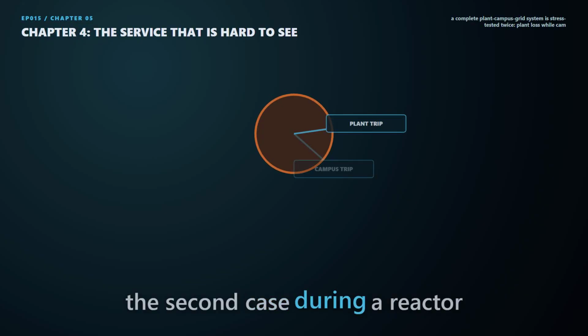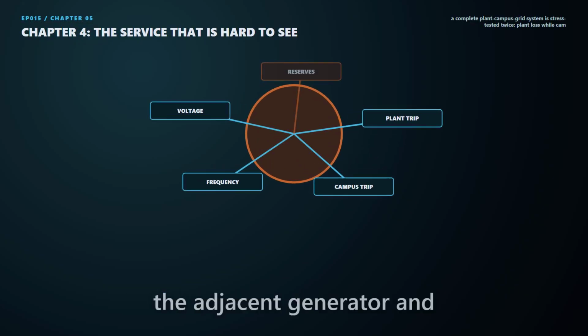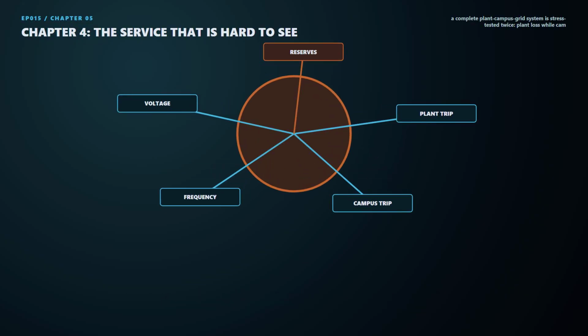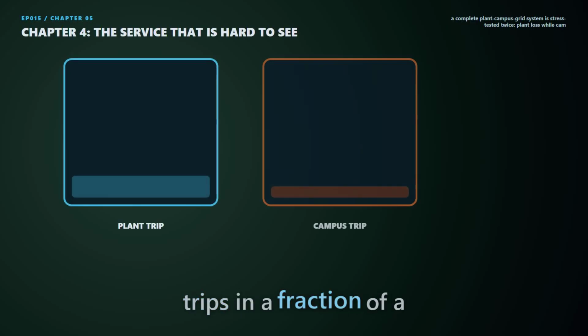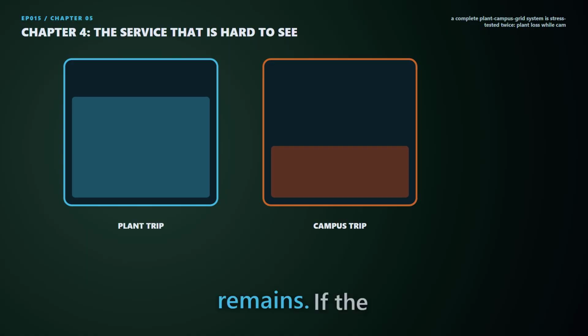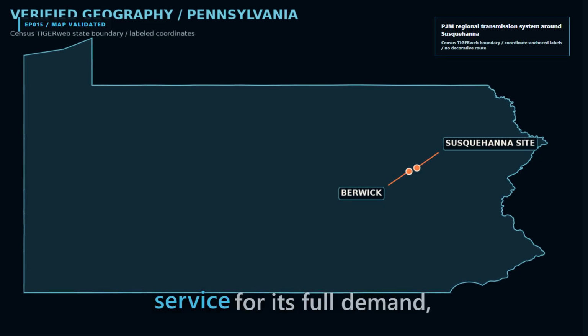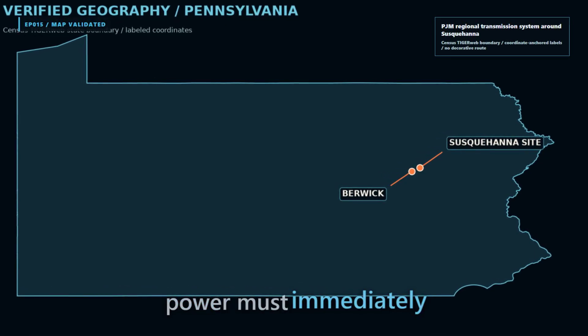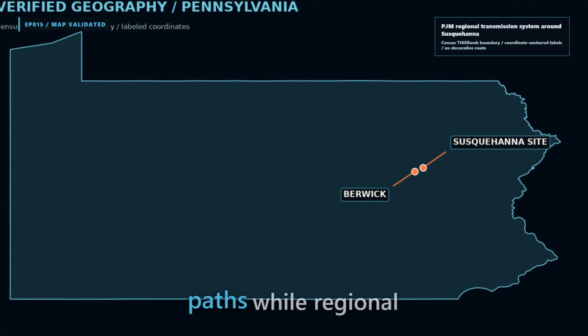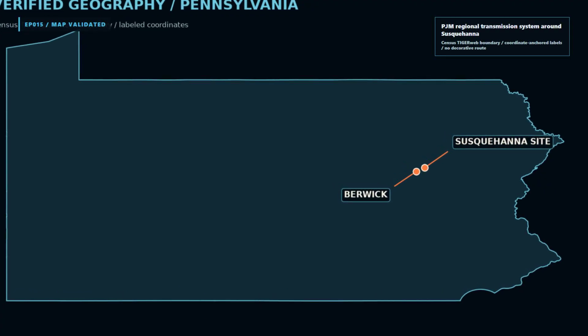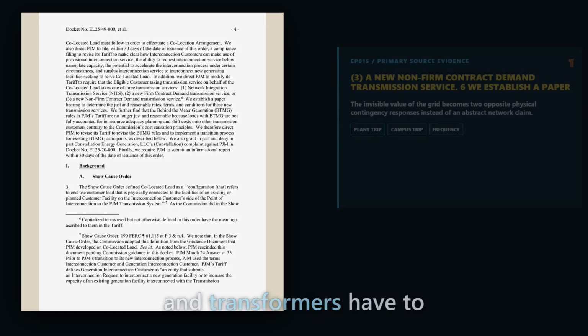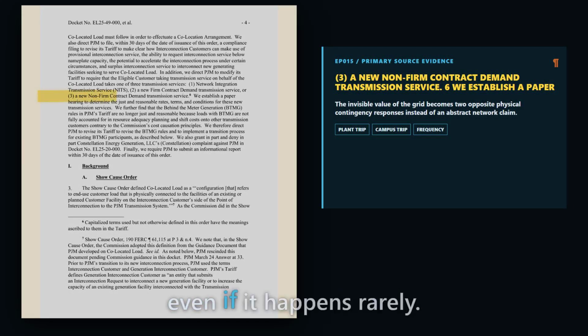Picture the second case during a reactor trip. Before the event, the adjacent generator and campus may look almost balanced. The plant trips in a fraction of a second, the data center load remains. If the campus has firm network service for its full demand, power must immediately arrive through other transmission paths while regional reserves replace the lost generation. Lines and transformers have to be sized for that transfer even if it happens rarely.